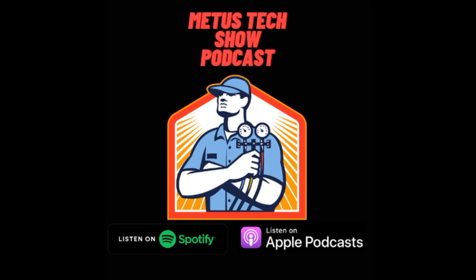Actually, with smart multi, we should be using Diamond System Builder software too, because on the older MXZ branch box systems, an MXZ 4C36 could take four indoor units, a 5C42 could take five. The smart multi took that nomenclature off. We literally had a call last week where a guy had five indoor units on a 3-ton, which can only take four, but there's nothing in the nomenclature that says it anymore. So if he'd have put it into Diamond System Builder, you would have found out. He would have found that as soon as he tried to add the fifth unit, it would have kicked him out.